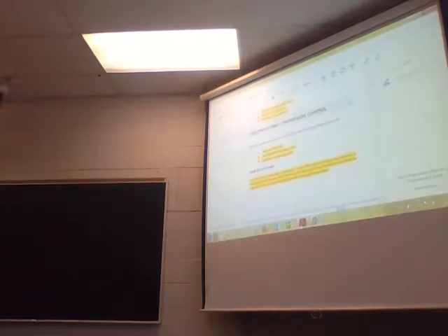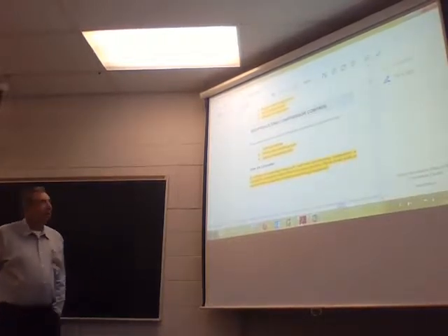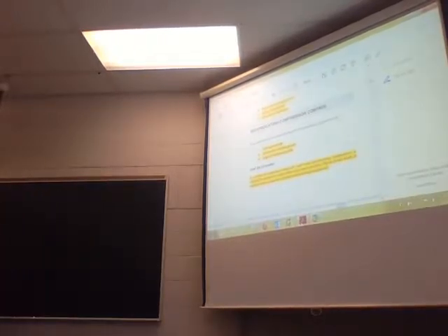Now we're going into constant speed. So, reciprocating compressor, constant speed. The best methods to control the load for reciprocating compressors are the inlet unloader, suction line unloader valve, or inlet air modulating valve. All right, so I'm pretty sure we're familiar with an inlet air unloader. Did that in 4th class. The method of unloading frequently used on reciprocating compressors is an unloader holding the compression inlet valve in the open position. That's what they call it, an unloader.